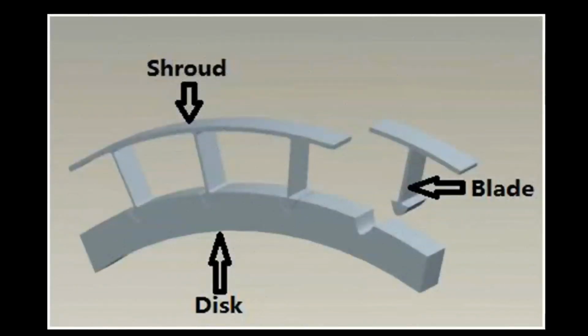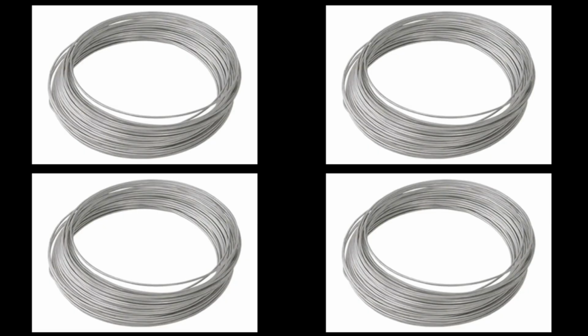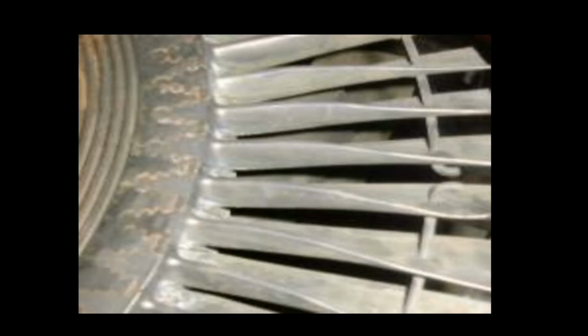Shrouds. Shrouds are used to reinforce the turbine blades' free ends to reduce vibration and leakage. This is done by riveting a flat end over the blades. In some cases, especially at the early stages, the shroud may be integral with the blade. When the blades are very long, as in the case of the last stage of a low pressure turbine, the rotor blades are further reinforced by using lacing or lashing wires, which circumferentially connect all the blades at a desired radius, and shrouding is eliminated.